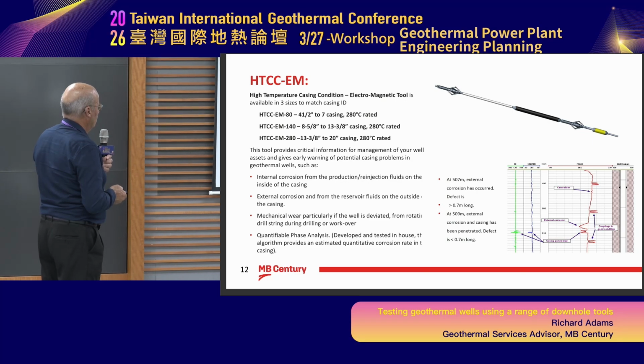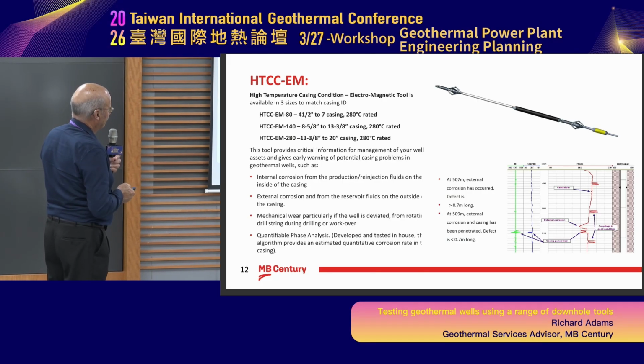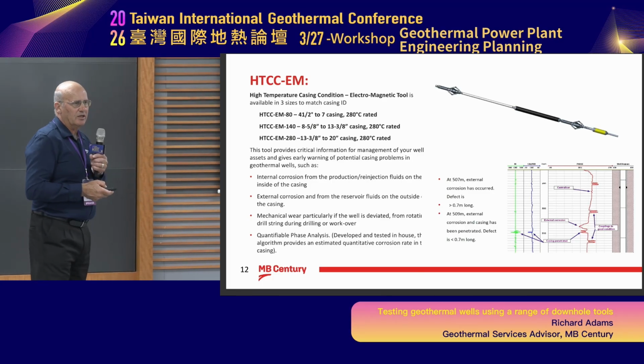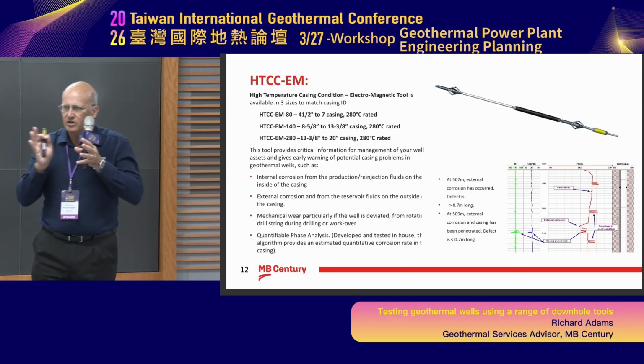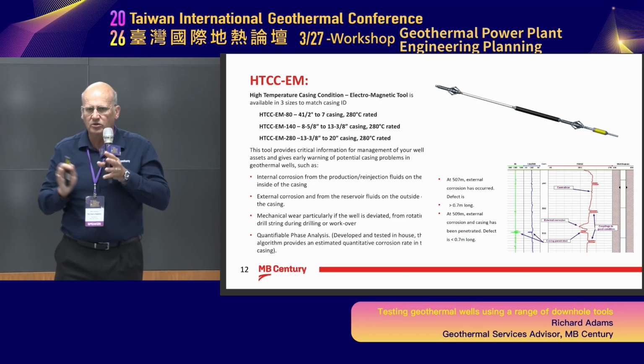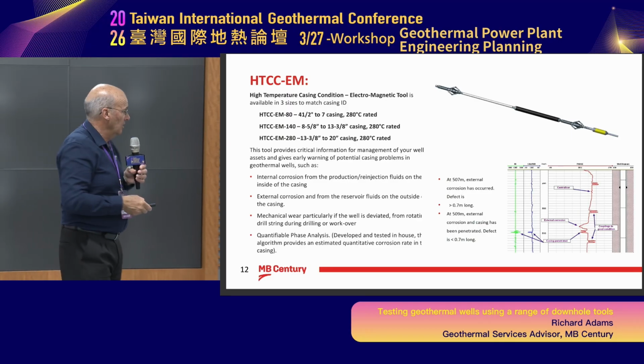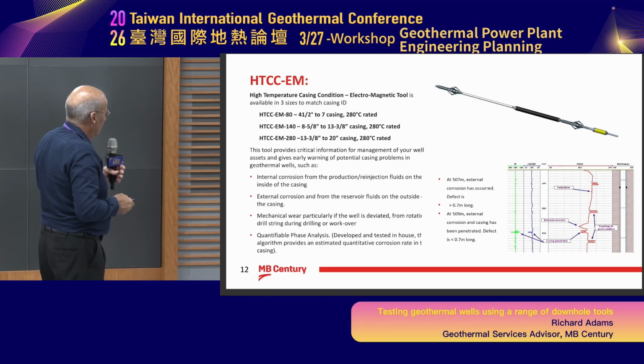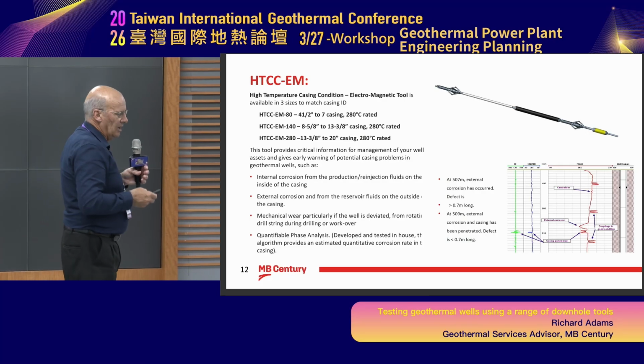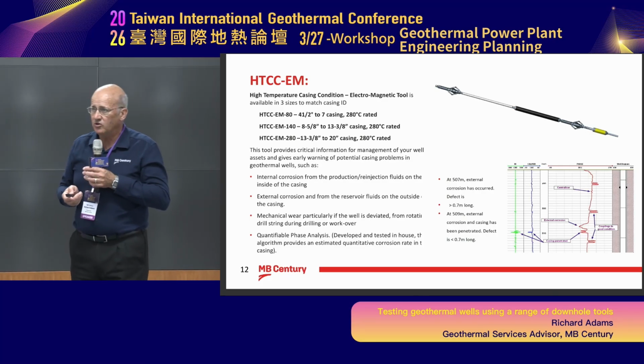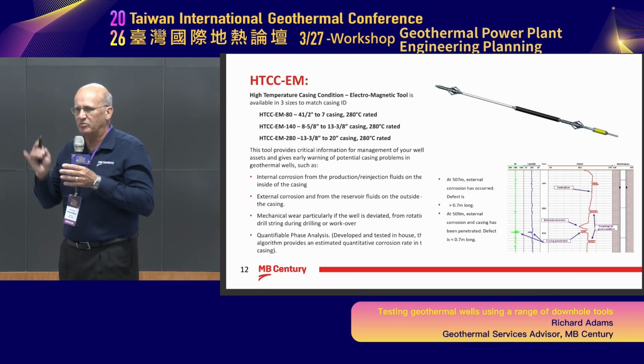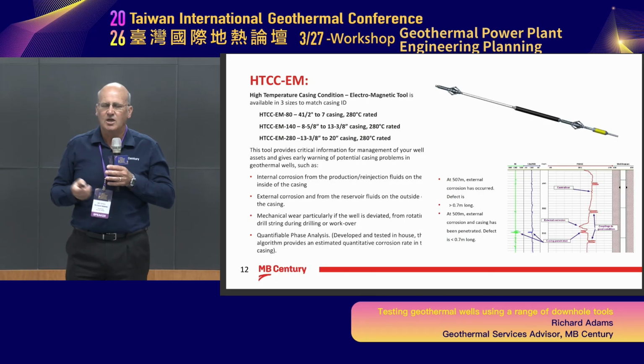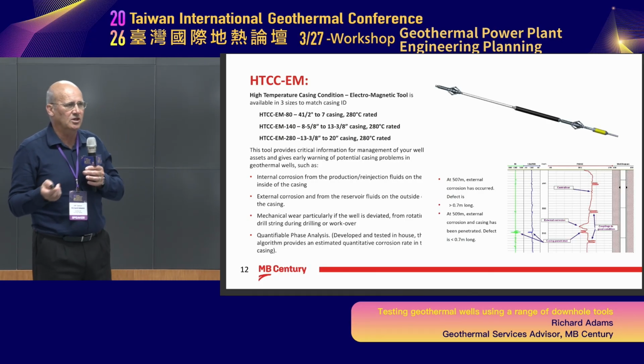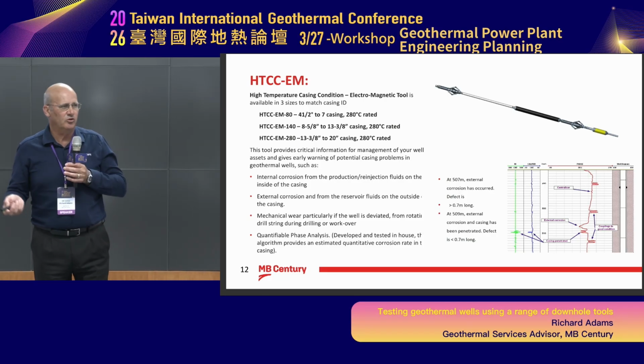And there's an issue right there. We've got 3 tools built into one. This here is a little tool we make, the round bit on the end, and it gives us ID change - electronically we can tell if the inside of the steel is changing, moving smaller. In the center of this tool we can measure the roughness of the casing inside, but the primary function is the phase change between the inside and outside of the casing, and we can pick up corrosion on the outside of the casing at 280 degrees Celsius, a kilometre or more underground.